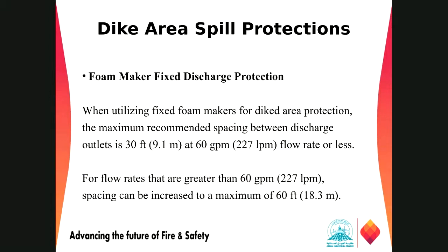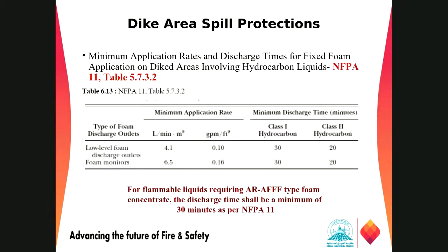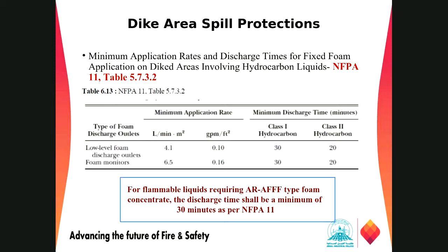What is the foam we are needing for that one? Because there is another criterion in NFPA that if we are using AFFF type foams, aqueous film forming foams, we have to take a minimum 30-minute discharge as per NFPA 11. So if you are using alcohol-resistant aqueous film forming foams, we have to select 30 minutes only, not 20 minutes. So maybe the foam we are using for this protection, regardless of the class of the hydrocarbon fuels, this requirement overrides that one. Yeah, very clear.